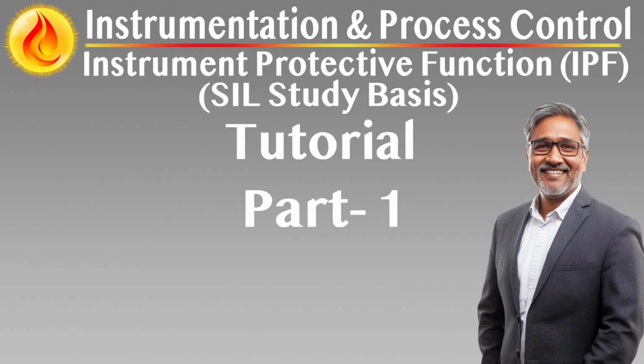Layers of protection analysis, LOPA. LOPA is used to quantify the residual risk after applying existing independent protection layers, e.g. relief valves, alarms with operator action, inherently safe design. If the residual risk remains above tolerable levels, an IPF is required.